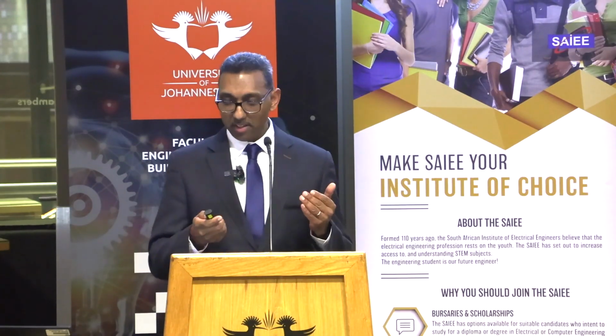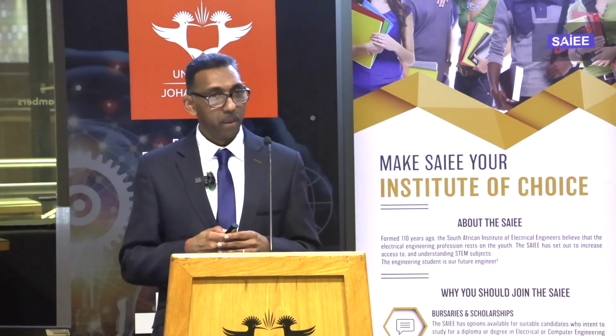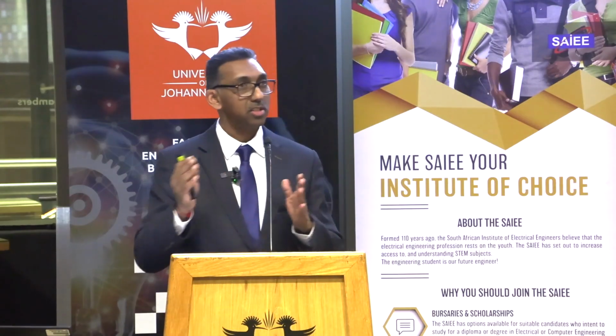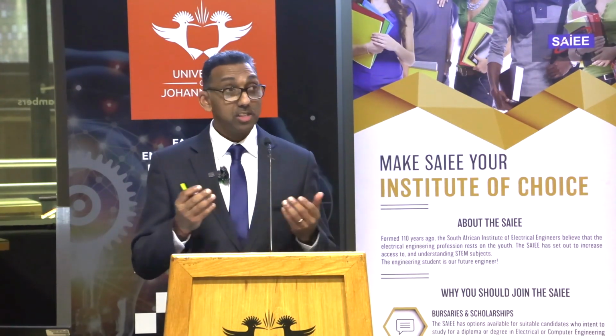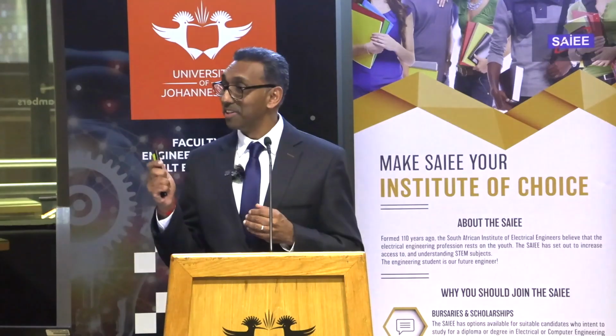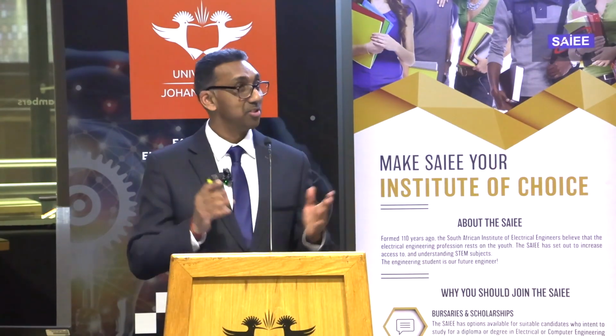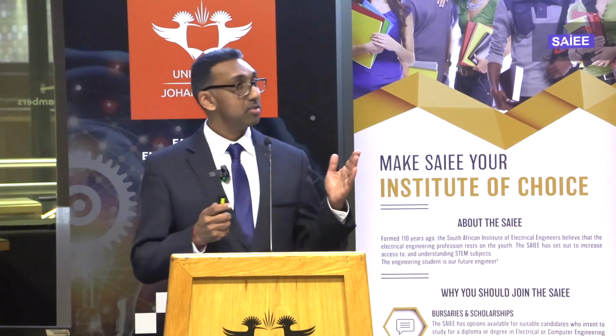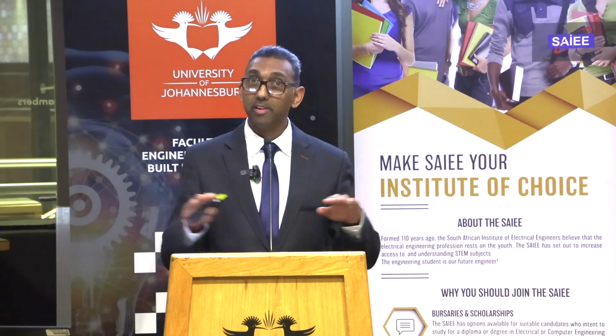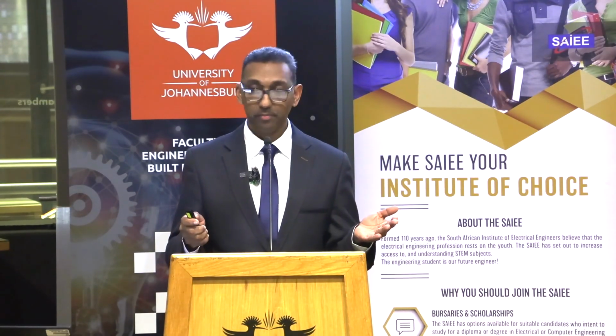We don't want load shedding, so they run for an hour, come down, then 3 hours later run again. The limiting factor for us is the number of starts. When we reach 250 starts, we do a minor inspection, checking parts without dismantling - it takes about a week. It cost a lot of money initially when the OEM did it, but our engineers learned how to do it, and now we don't pay for that inspection - we do it in-house. But the other challenge is once you reach 1,500 starts, you cannot operate the unit until you do a major overhaul.